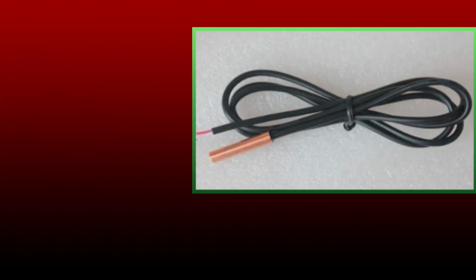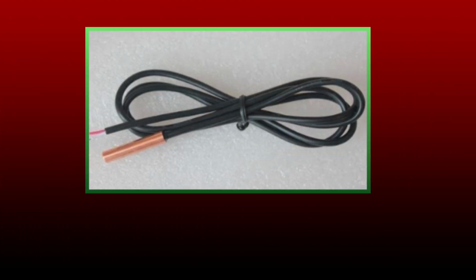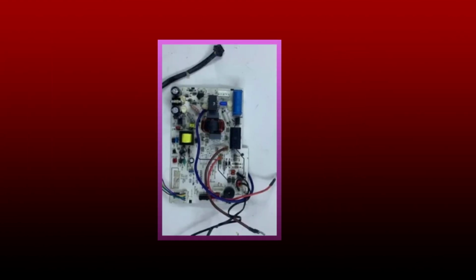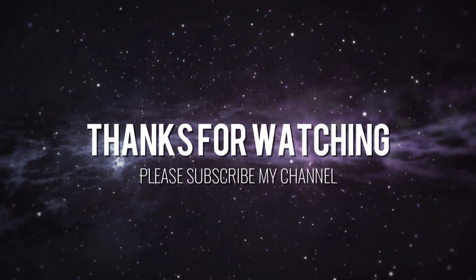And if it is still not fixed after that, then you can replace the evaporator temperature sensor, the coil sensor. Then this error will be completely fixed. Generally this error occurs due to a sensor problem. Most of the time this problem gets completely cured by changing the sensor. And if this problem is not fixed after changing the sensor, then you will have to change the power circuit board.